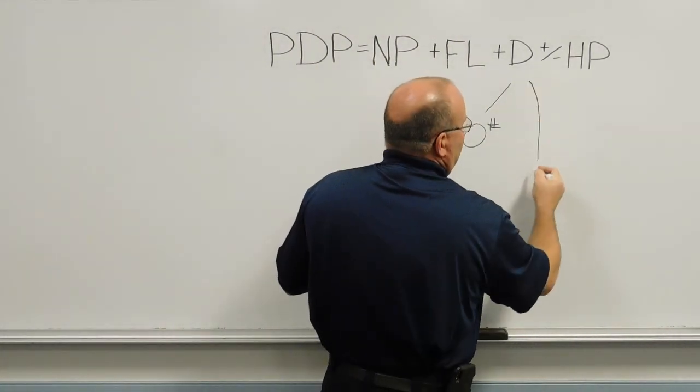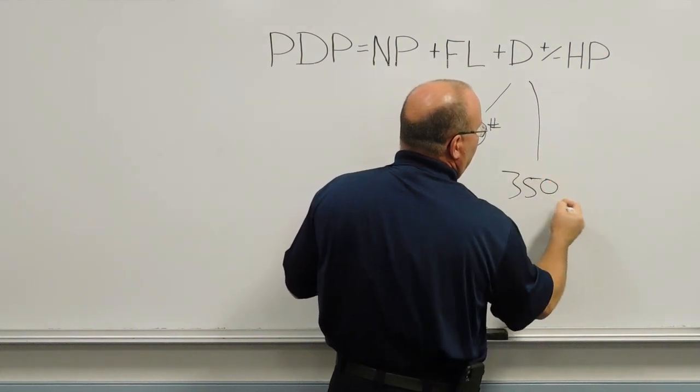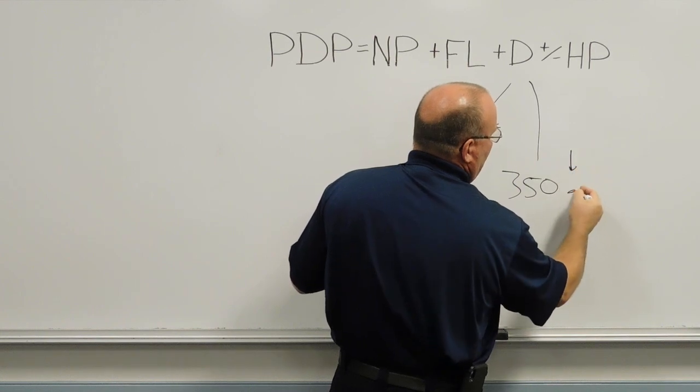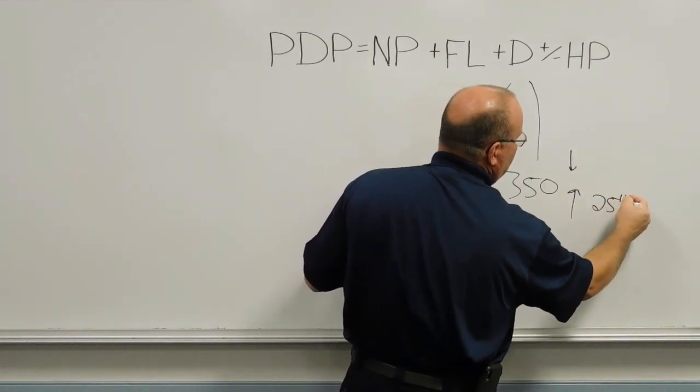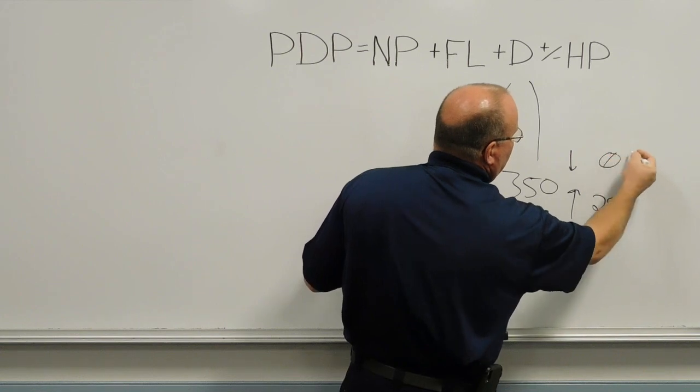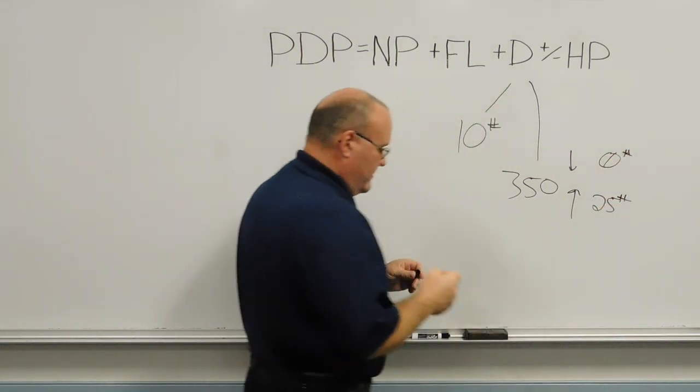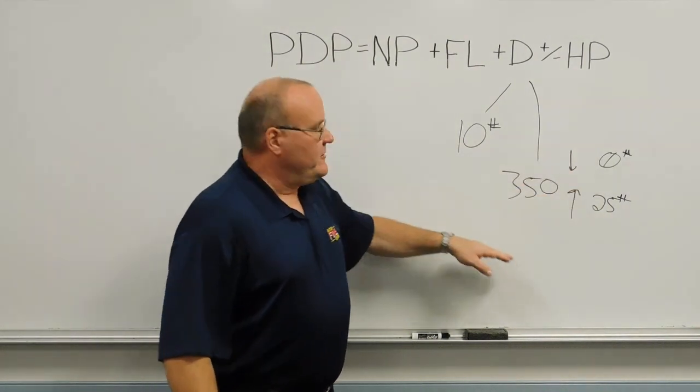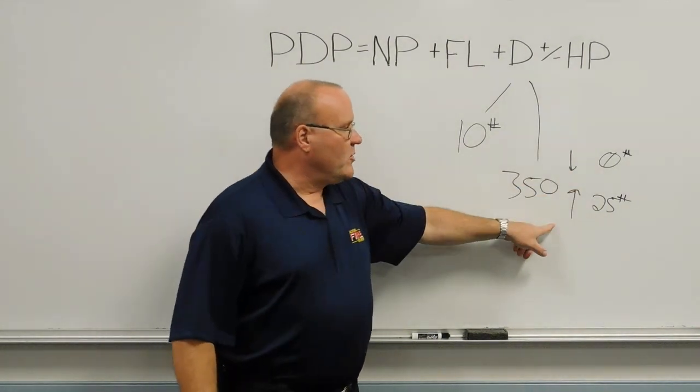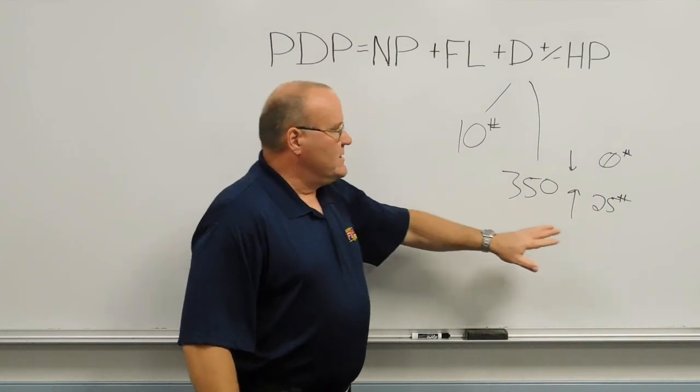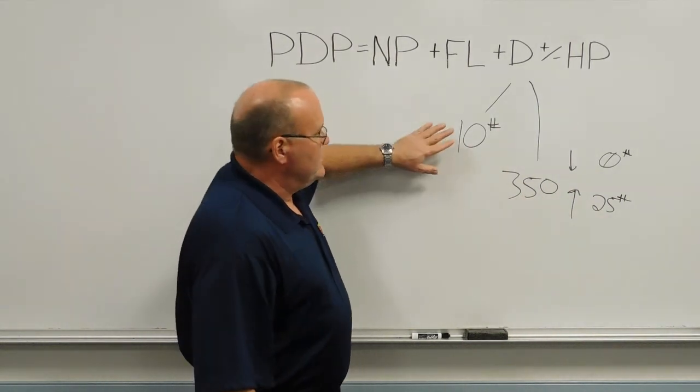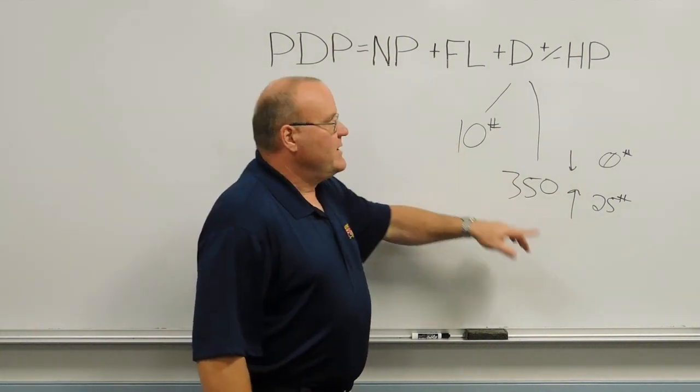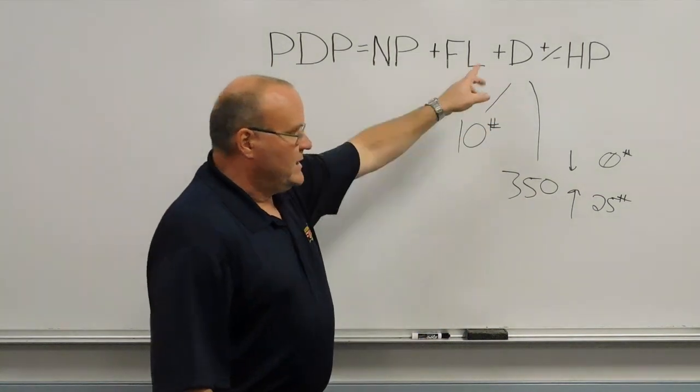Some people use the flow, and they will come up with a friction loss number or a device number based on the flow through the device. If they're flowing 350 gallons a minute or less, they count zero. If they're flowing 350 gallons a minute or more, they would give it 25 pounds for that device. So whichever method you use, whether you're using 10 pounds per device or accounting for the friction loss in the device based on flow, make sure you account for it and plug it in here under devices.